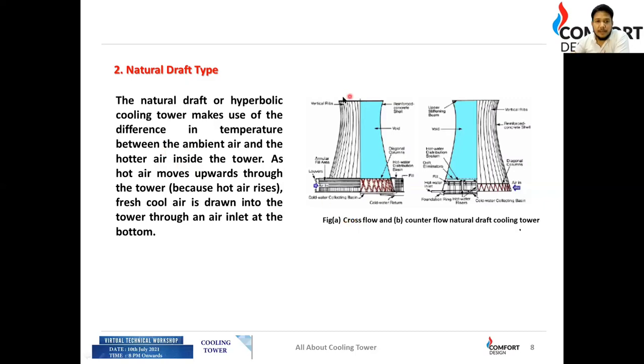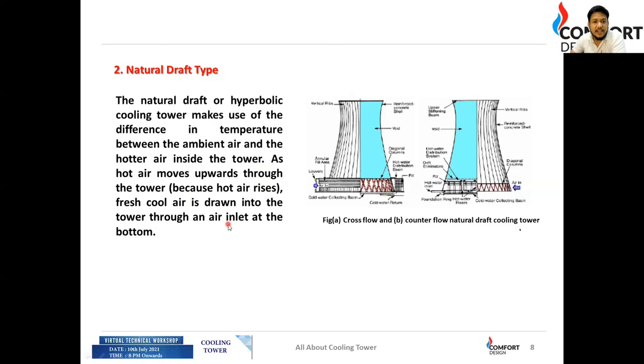The second air draft type is the natural draft tower, also called hyperbolic because of its shape. These towers use the temperature difference between ambient air and the hotter air inside. Hot air rises upward through the tower, and fresh cool air is drawn in through an air inlet at the bottom. This cools the water, which is then supplied to the application.